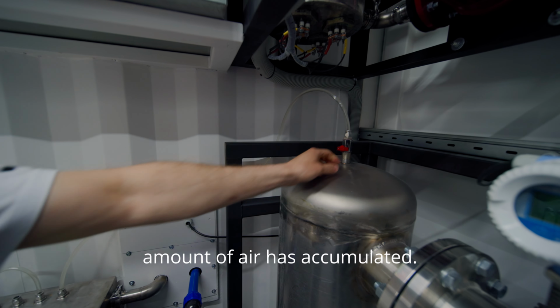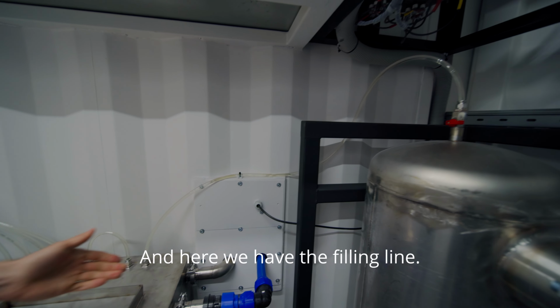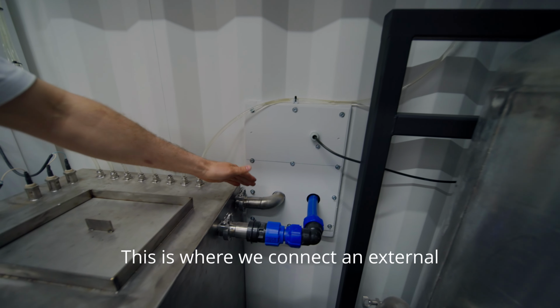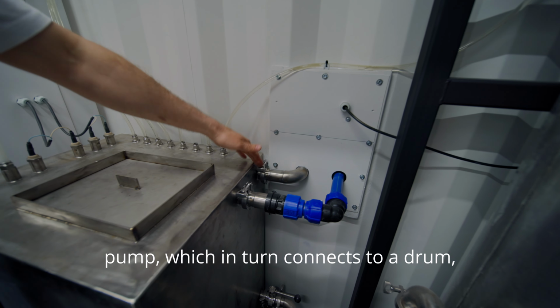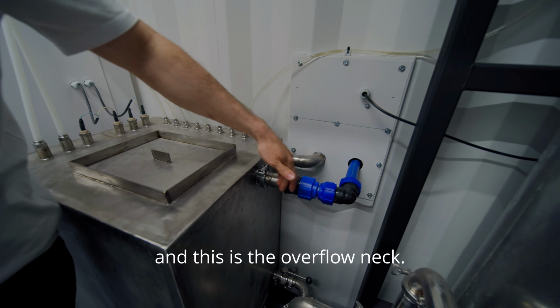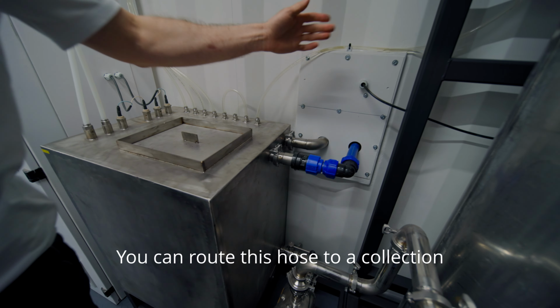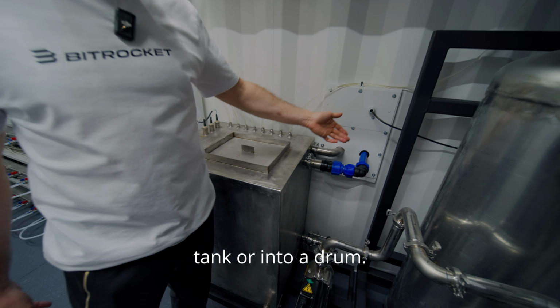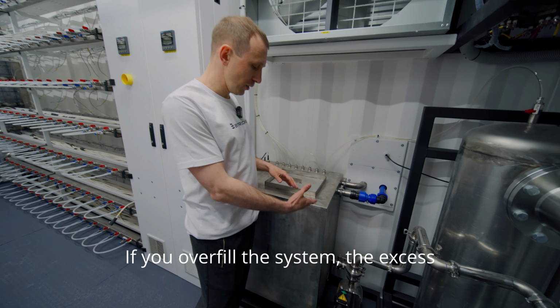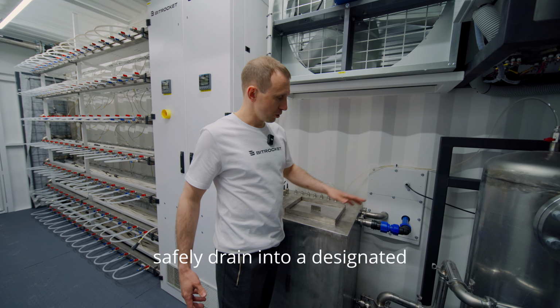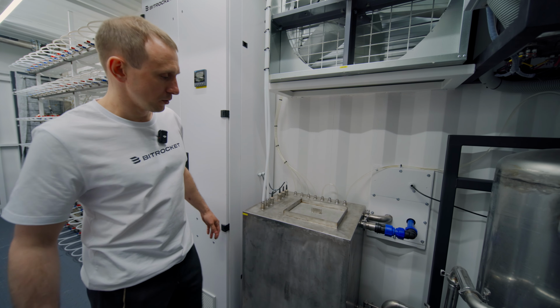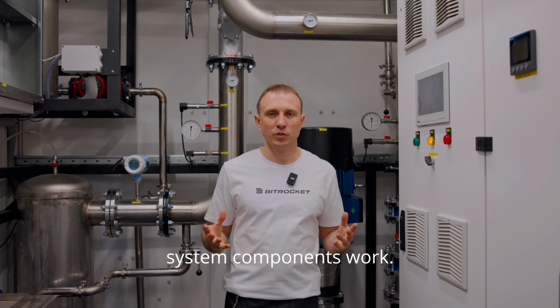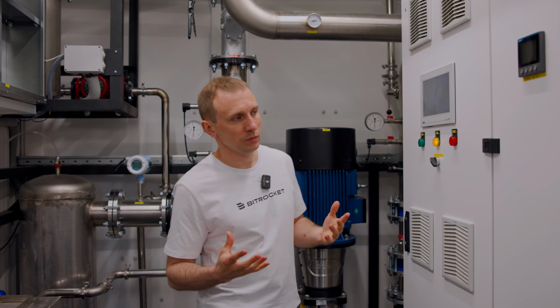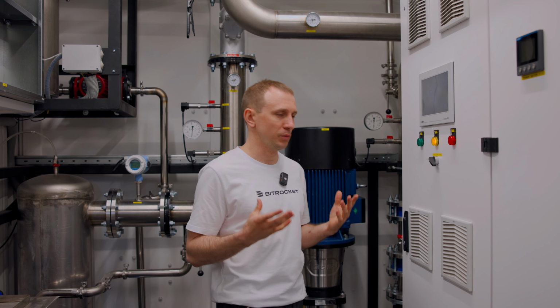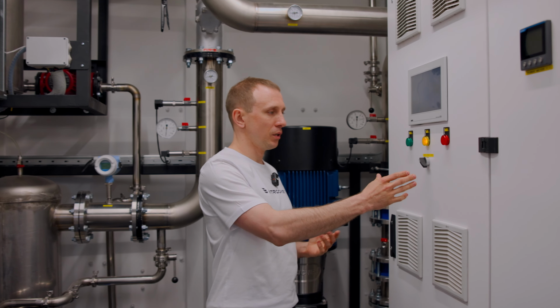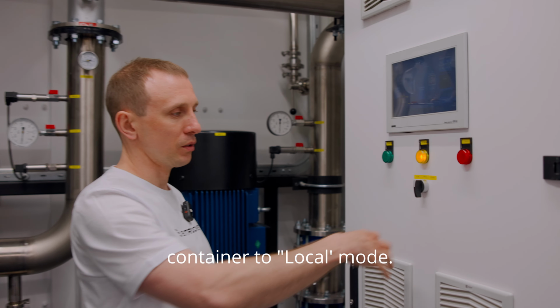You can see a small amount of air has accumulated. And here we have the filling line. This is where we connect an external pump, which in turn connects to a drum. And this is the overflow neck. You can route this hose to a collection tank or into a drum. If you overfill the system, the excess ethylene glycol will safely drain into a designated container. Now you know how all the system components work. Let's start the system in real time. Get into operational mode. First, we switch the container to local mode.